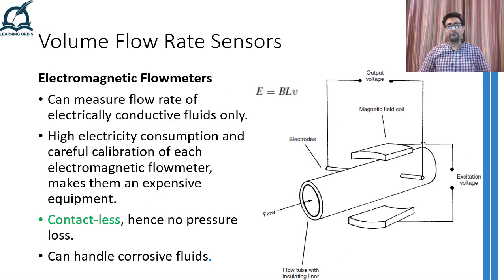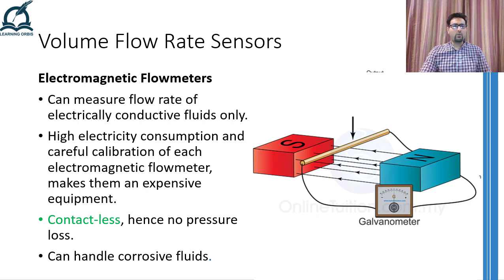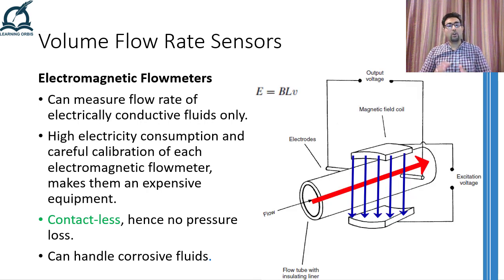The next volume flow rate sensor is known as the electromagnetic flow meter, which is a non-invasive and almost contactless transducer. The electromagnetic flow meter can measure the flow rate of electrically conductive fluids only, because the working principle includes generation of a magnetic field through which the fluid flows. It is exactly equal to a conductor wire moving inside a magnetic field — whenever this happens, a voltage is induced into the conductive wire. Therefore, if the conductive fluid is flowing past an orthogonal magnetic field, then a voltage will be induced in it according to Faraday's law given by this equation.